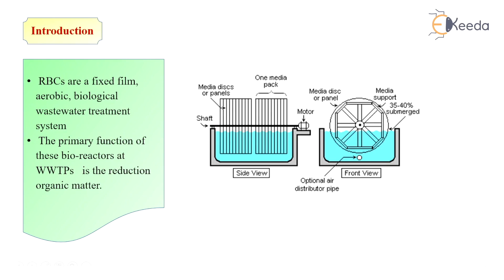As you can see in this picture, this is the schematic diagram of rotating biological contactors. The rectangular tank contains sewage or wastewater. There is a circular rotating disc made up of plastic material which rotates around a circular shaft. The disc is continuously rotating, with approximately 35 to 40 percent of the disc immersed in the sewage and the remaining part open to the atmosphere.